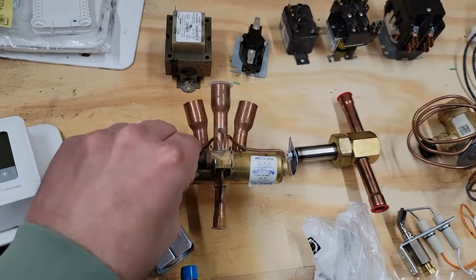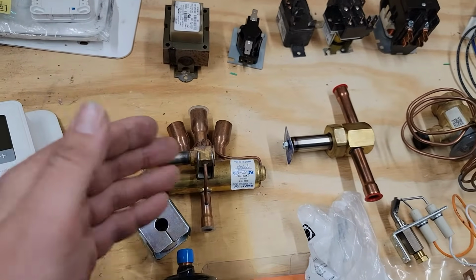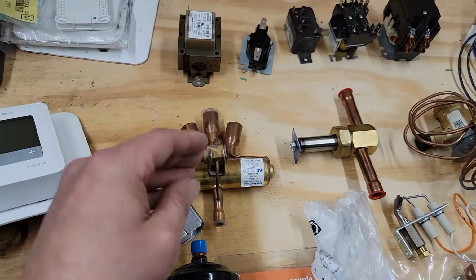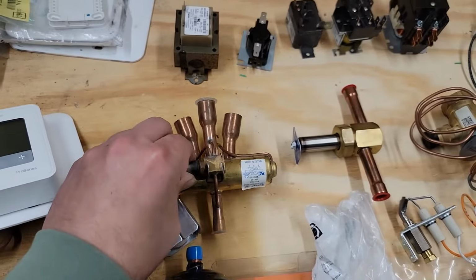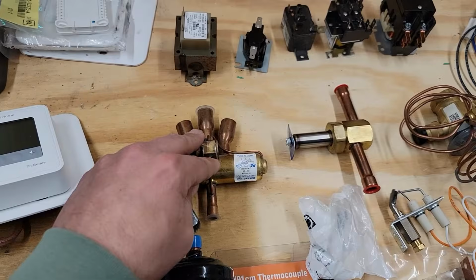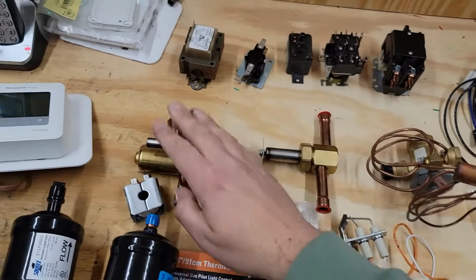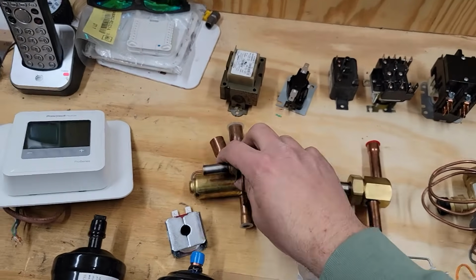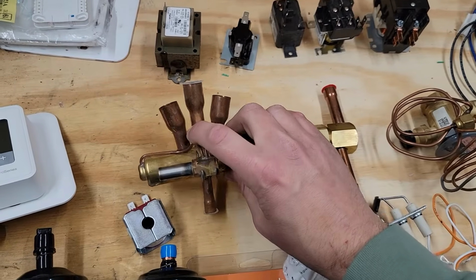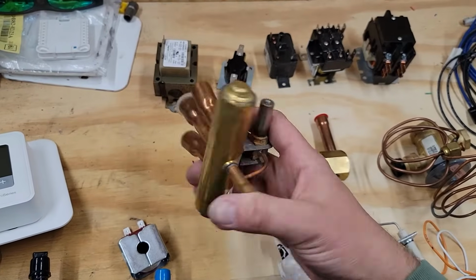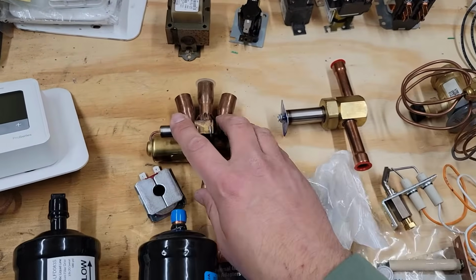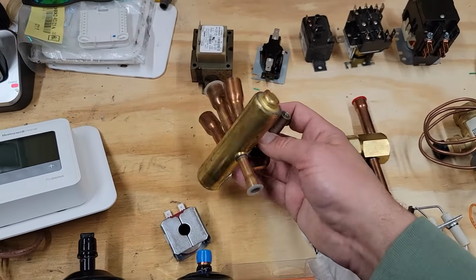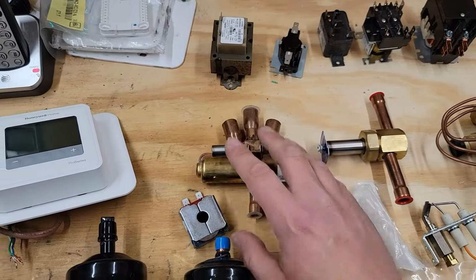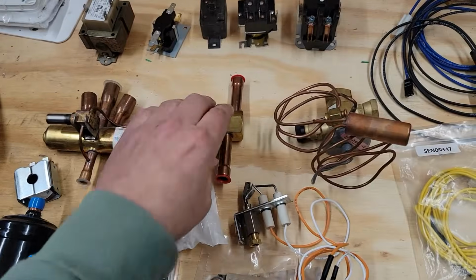Rheem and Ruud energize in B, and then most other brands like York, Trane, American Standard, Carrier, they energize in O, so energize the valve in cooling. So you'll learn more about that, but this is a reversing valve. It's not a very easy part to change. Depends on how big the valve is and how easy you can get to it. And this part doesn't normally go bad, but I have seen some go bad and had to replace some.